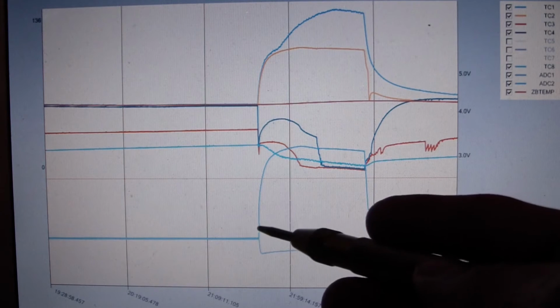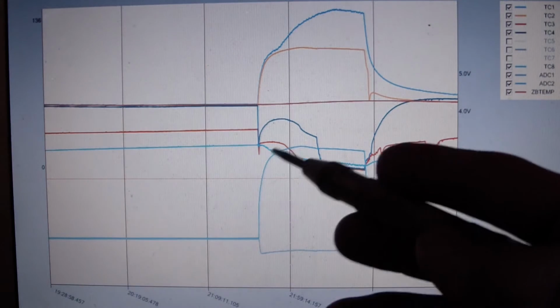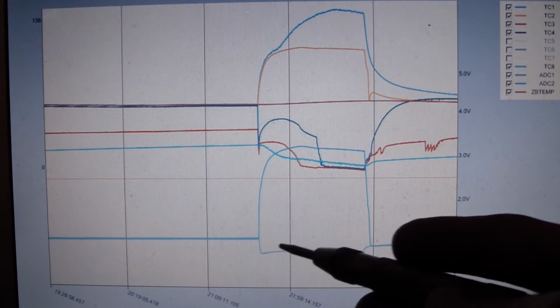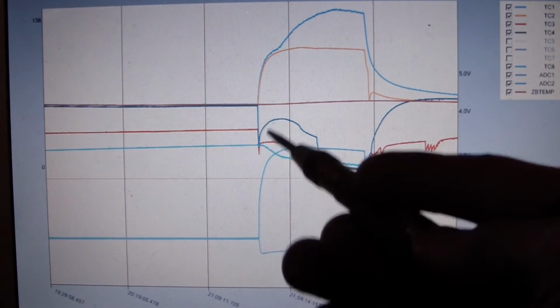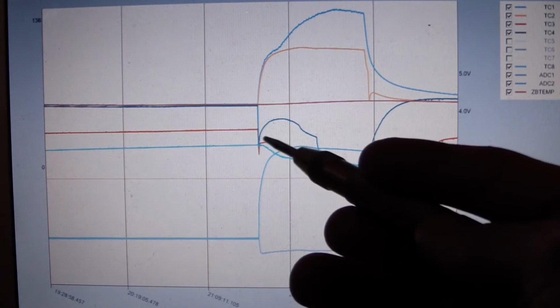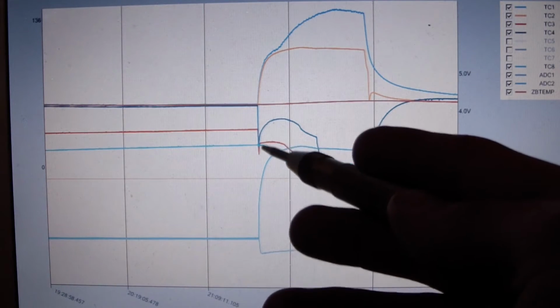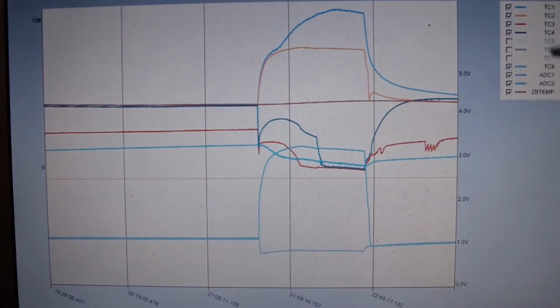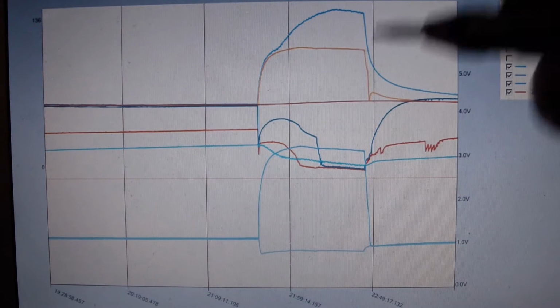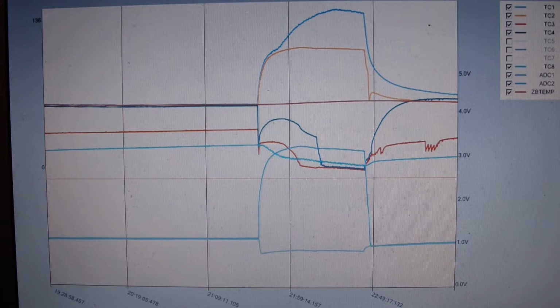So whenever the machine first kicks on, obviously the high side pressure starts to rise a bit and the low side drops off rather rapidly. We get this downward spike. These are the superheats, the one before and after the heat interchanger. The red one is interesting because it drops pretty suddenly. The blue one drops a little bit. That's after the heat interchanger. Of course, it's going to be a little bit warmer because you have the cap tube wrapped around it. It's in an ambient environment, so it's going to be warmer anyway.